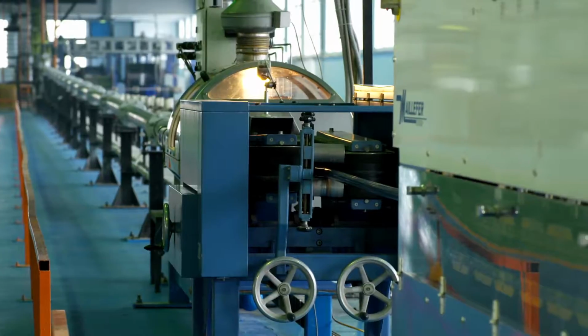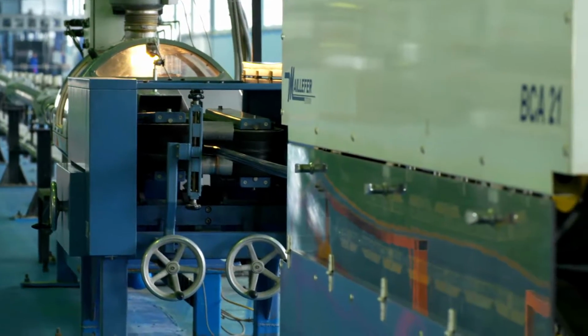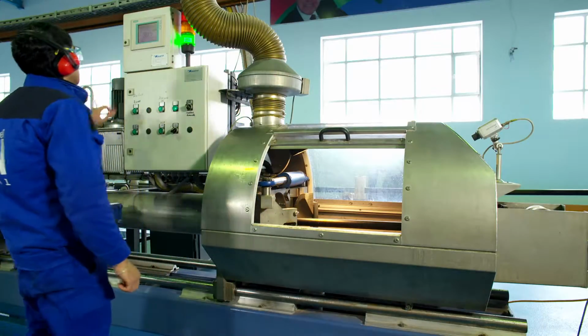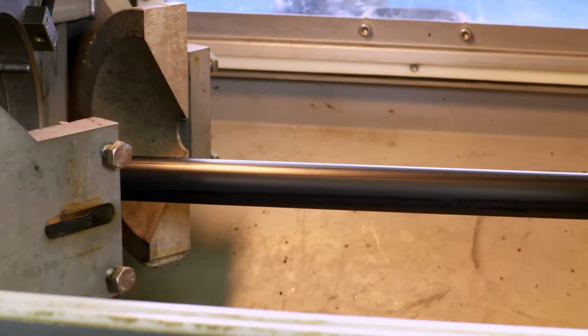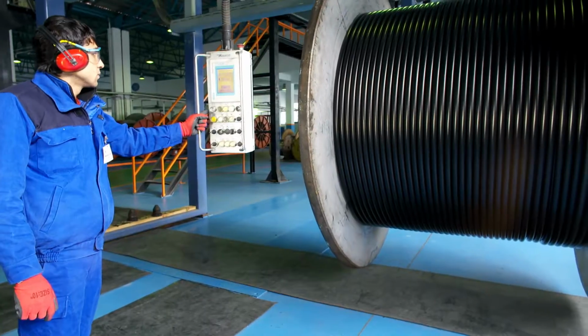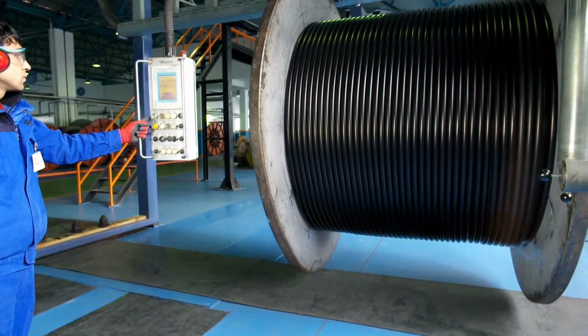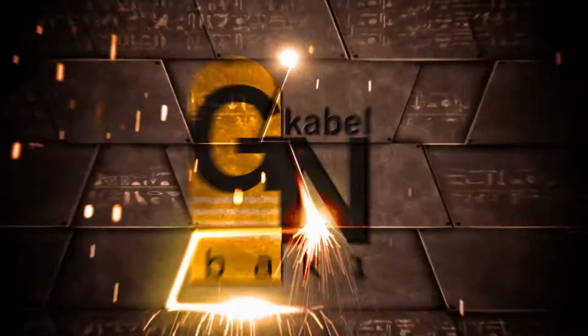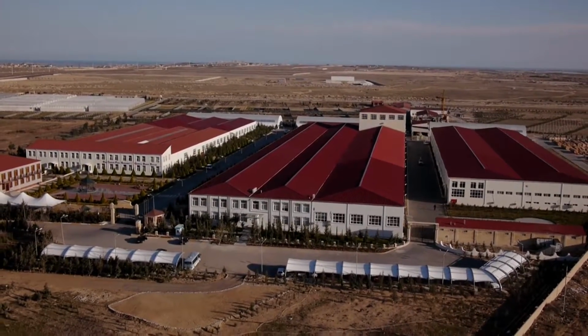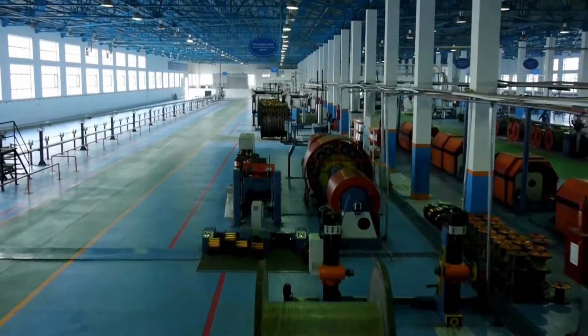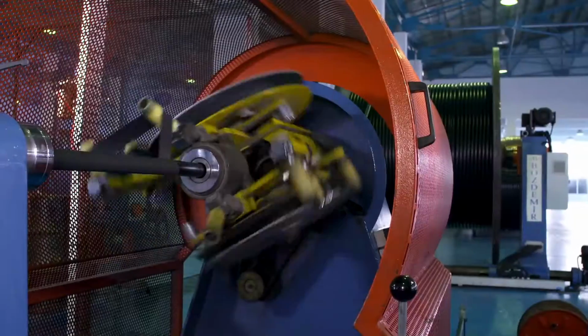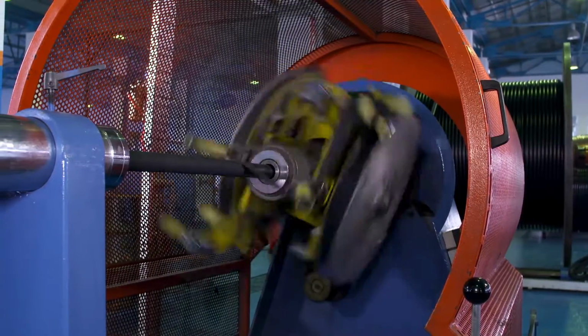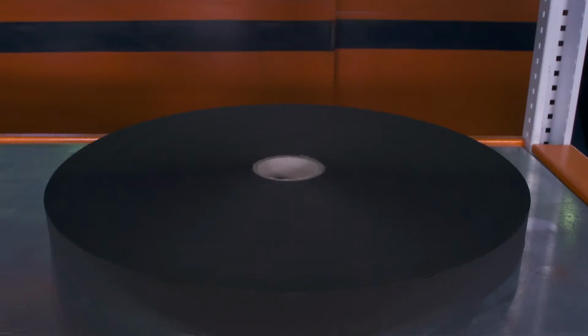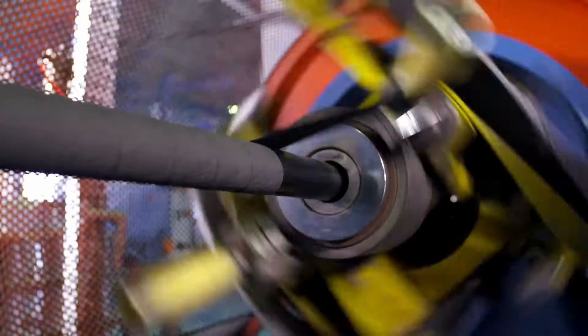After the cross-linking process, the insulated core is cooled in the 90-meter cooling tube by water circulation. The cooling is followed by the process of drying in special equipment. From here, the cross-linked insulated core is sent to the next production step. The next step is the screening process. The screening layer could include some special tape depending on the customer's request. Both semiconductive crepe paper and semiconductive swelling tape, which is called water blocking tape, are mainly used under copper wire screening as a protective barrier.